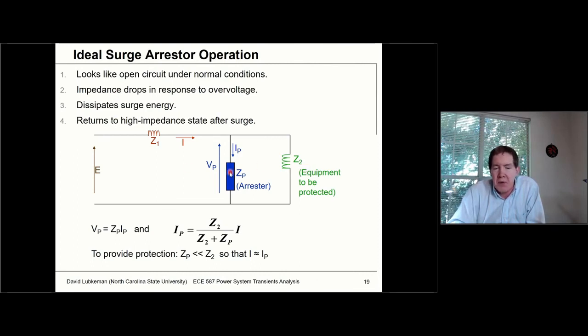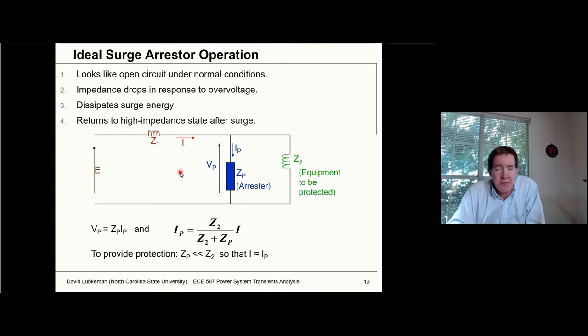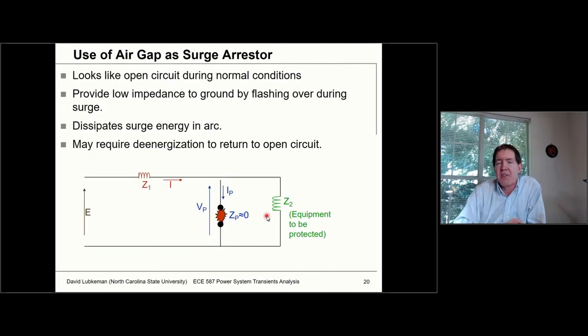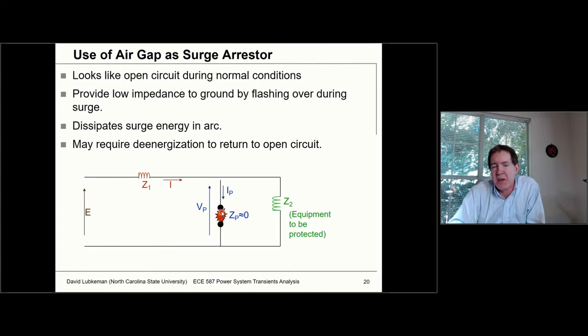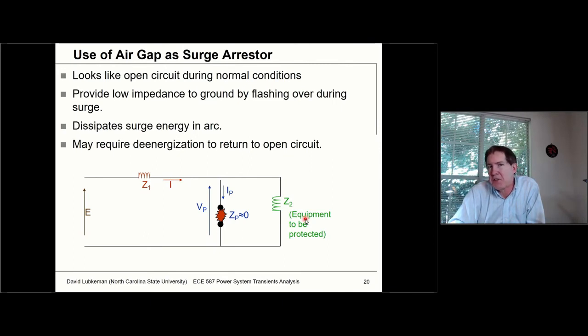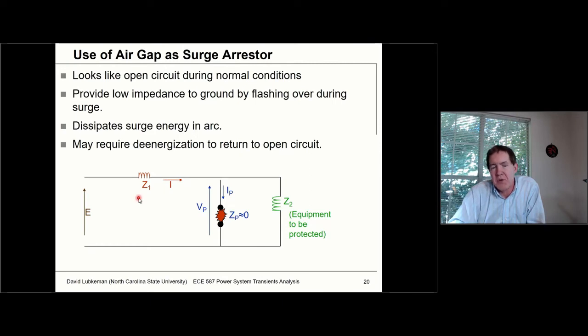The early technology was simply an air gap — going back to Benjamin Franklin days. When the voltage gets too high, the small air gap's insulation fails, shorting out and routing the surge energy to ground. This would be the cheapest protection option. The gap stays ionized as long as the overvoltage drives the circuit, and when the overvoltage is gone, the air de-ionizes and it's self-healing insulation.